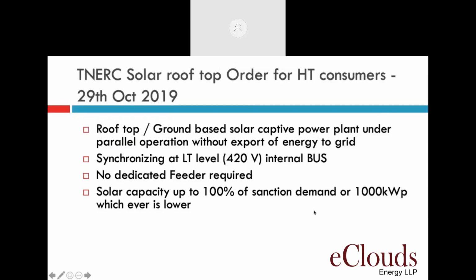So let me start with the policy. What is there in the policy? Rooftop or ground-based solar power plant under parallel operation without exporting to the grid is allowed. Synchronization at LT level, that means your internal bus. Even though you have an HT service, you can synchronize the solar with your LT service, provided there is a reverse power relay. So it's a zero export system. No power is to be exported into the grid. It is 100% utilized by the factory or the commercials. And no dedicated feeder is required.